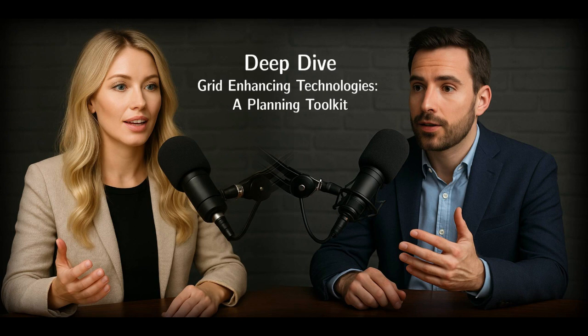Are there advancements in pumped hydro too? Yes. Advanced pump storage units now feature variable speed turbines and pumps, offering more flexibility. There are also ternary units that can operate in pumping, generating, or synchronous condensing modes for reactive power support. And new designs explore underground reservoirs or using seawater for coastal installations. So it's an evolving technology too.